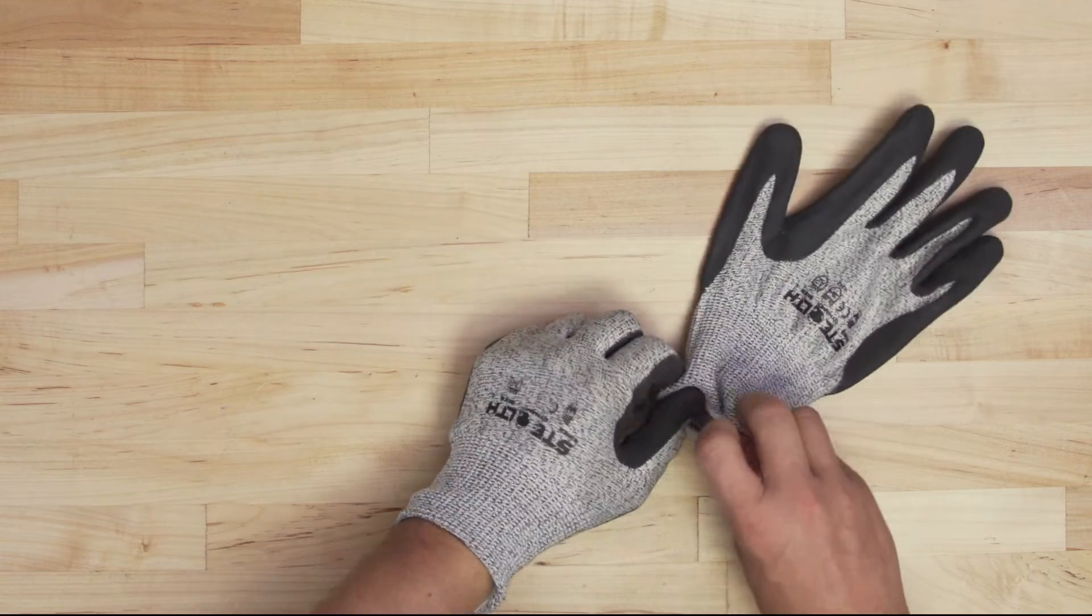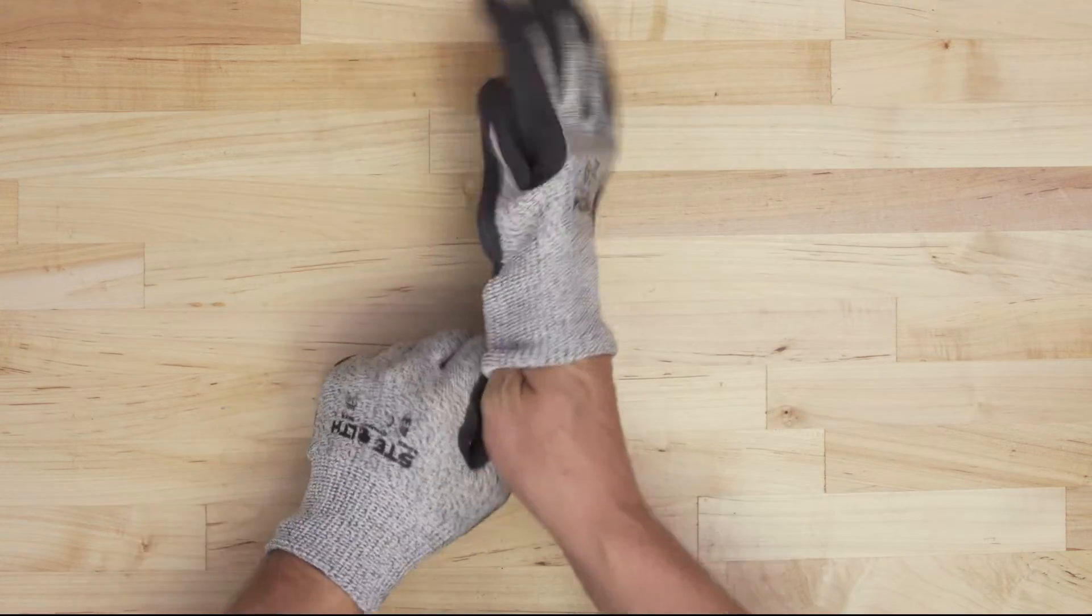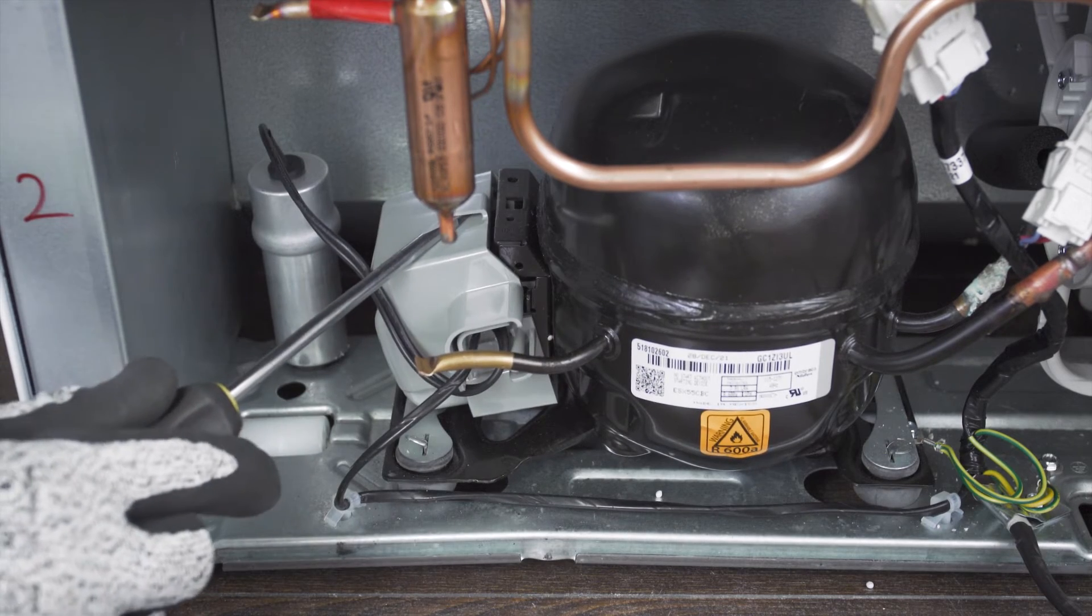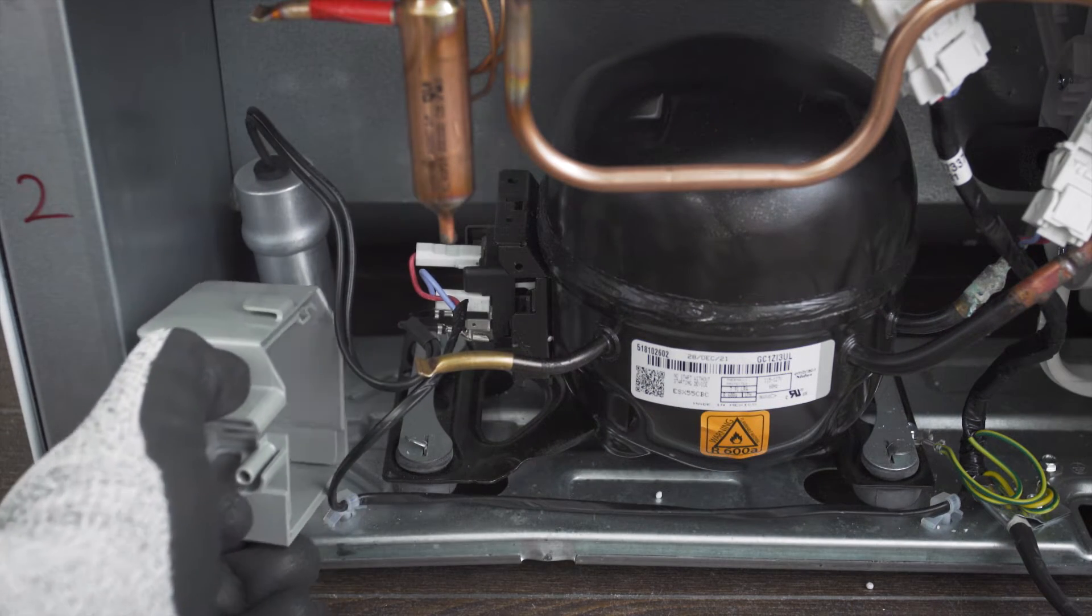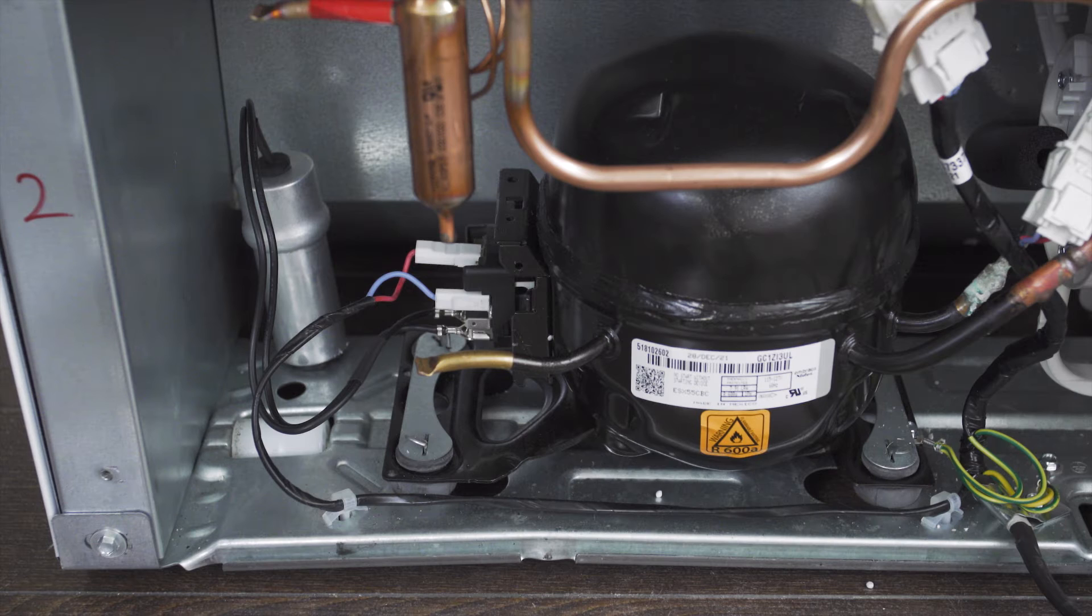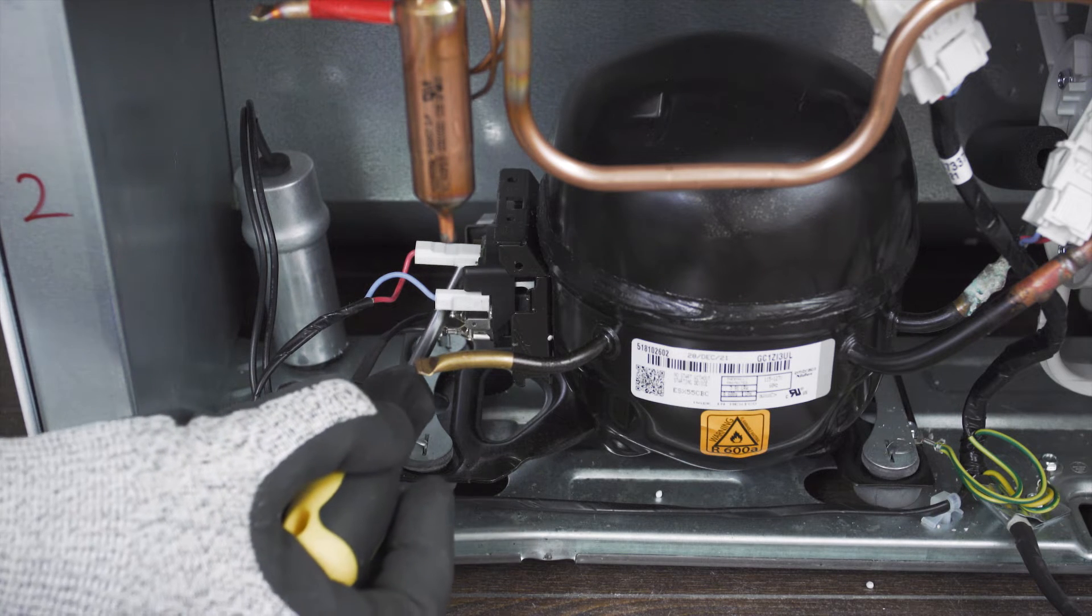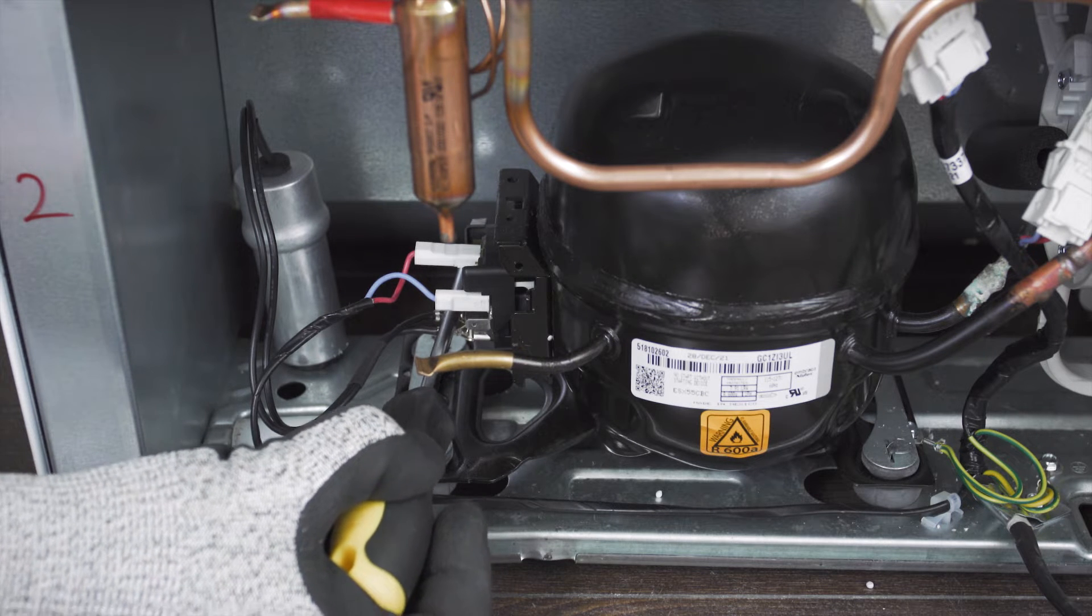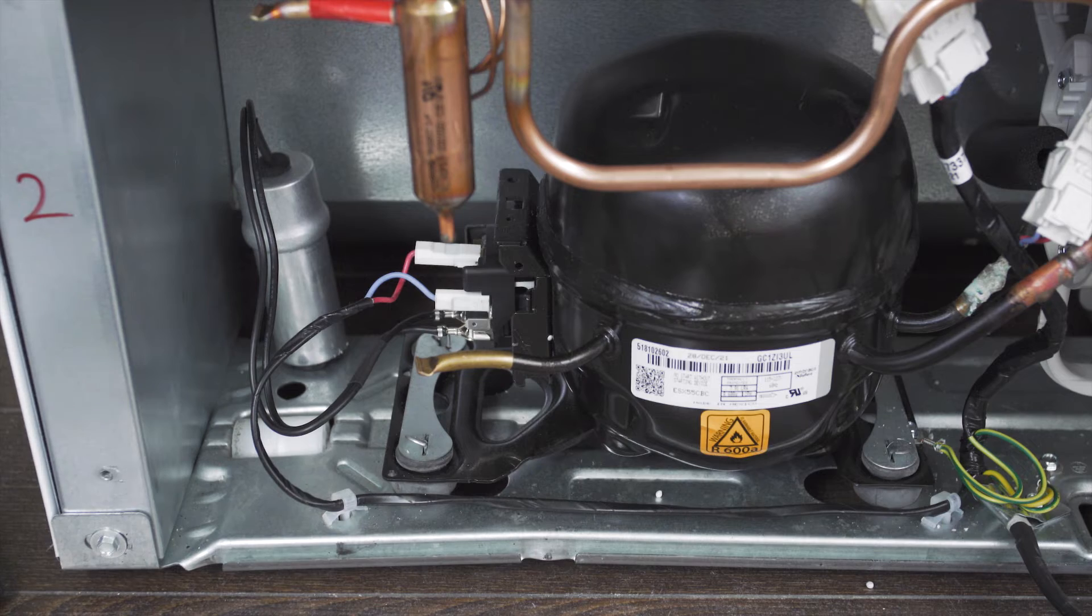When accessing the compressor components it's best to wear cut resistant gloves. In some models you'll have to remove a cover. The capacitor stores and releases an electrical charge. So be careful of any exposed terminals as it can still give a shock. Before anything else use a high ohm resistor or a screwdriver with an insulated handle. Touch between the two terminals to release any stored energy inside the capacitor.